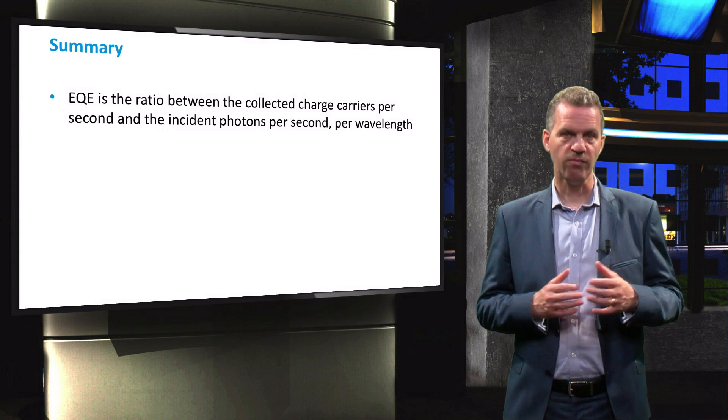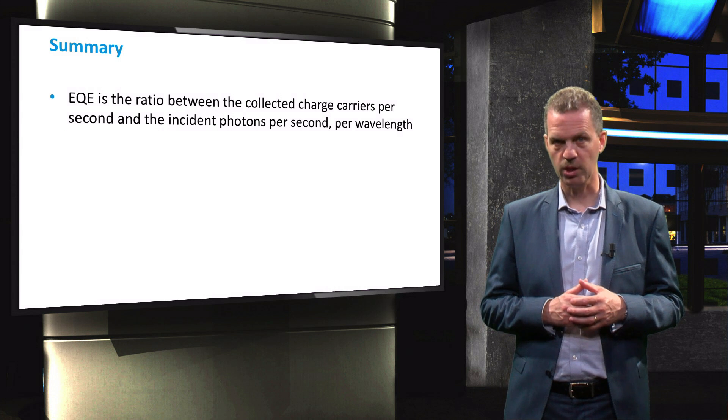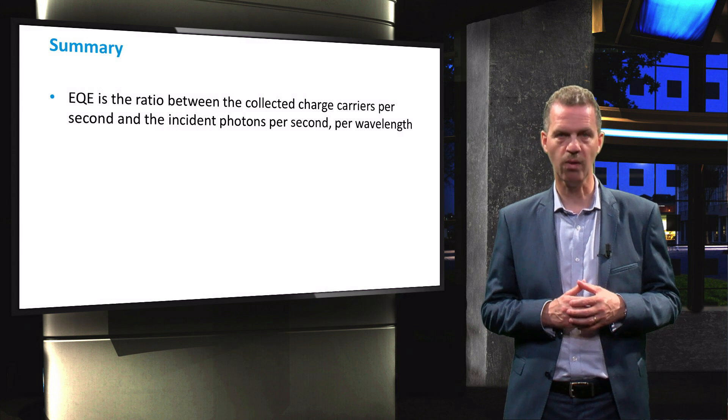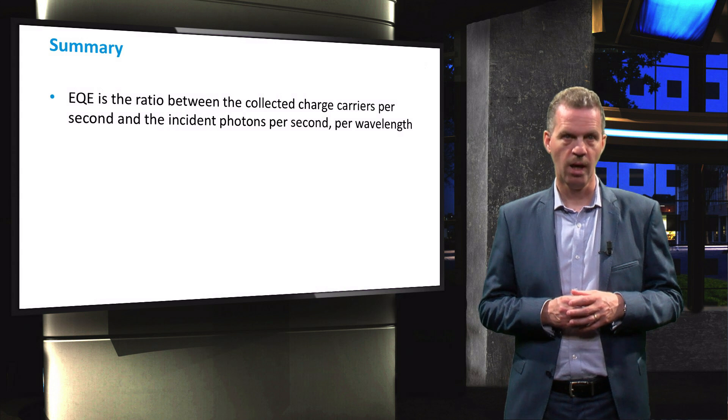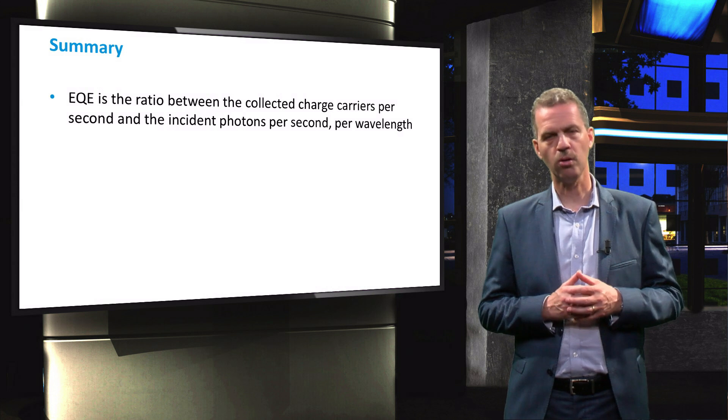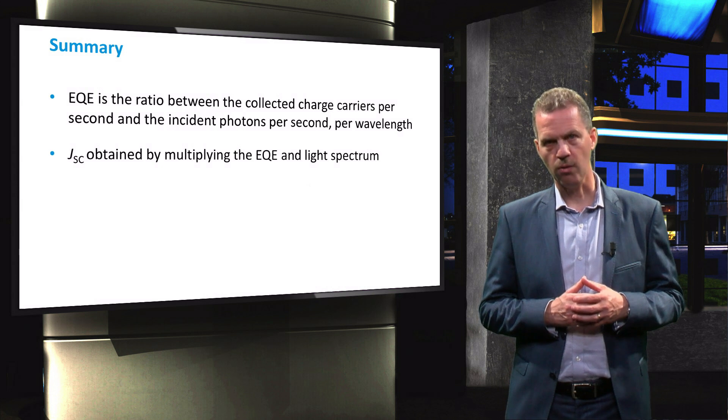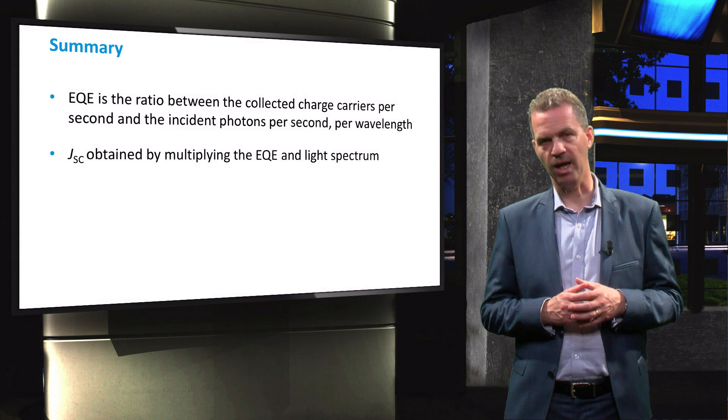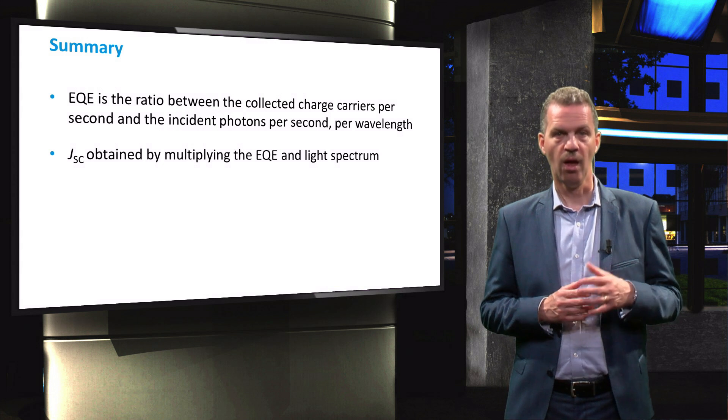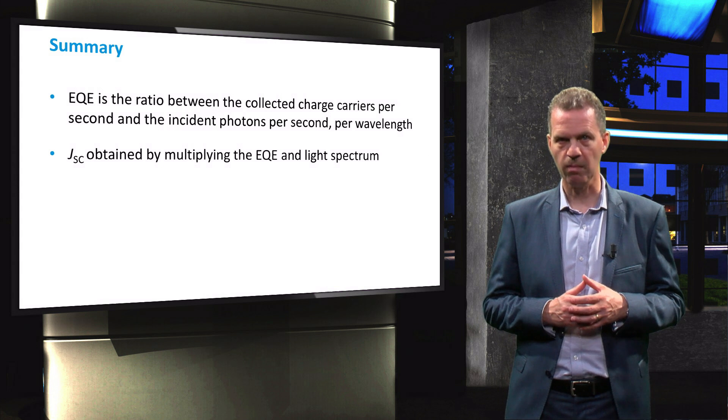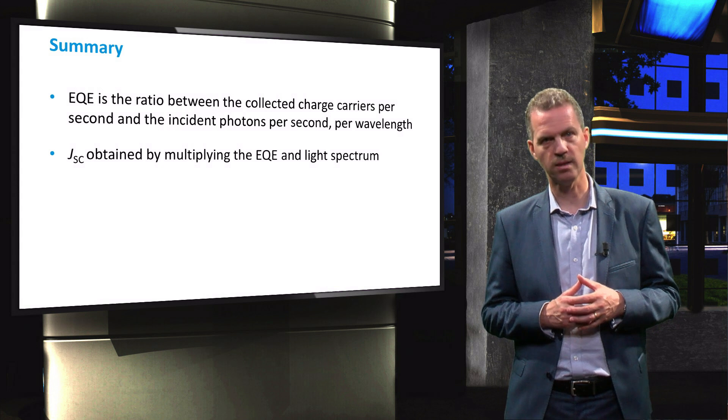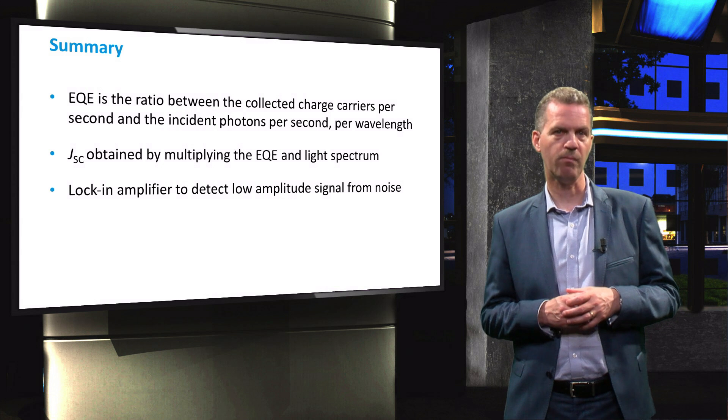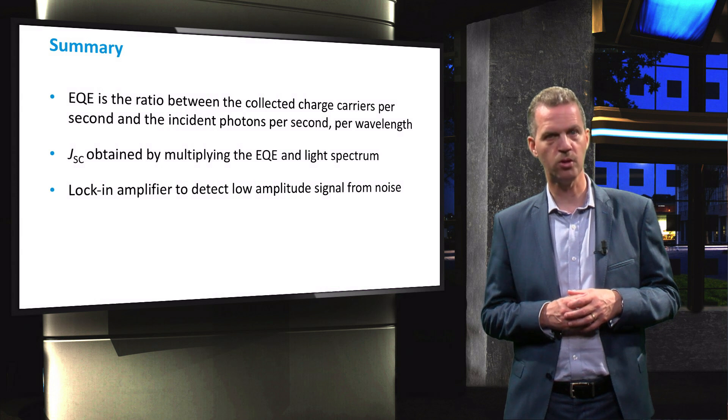To summarize this video, we have discussed the definition of the external quantum efficiency as the ratio between the collected charge carrier flux and the incident photon flux for each wavelength. By measuring the reflectivity of the solar cell, it can be transformed into the internal quantum efficiency. The short-circuit current density of the solar cell can be determined accurately by multiplying the EQE with the solar spectrum and integrating over all wavelengths. This value can be used to correct for the spectral mismatch of the solar simulator used for the illuminated JV curve measurement. Finally, we have discussed the basic EQE setup with a lock-in amplifier as an instrument to obtain the low-amplitude measurement signal from noise.